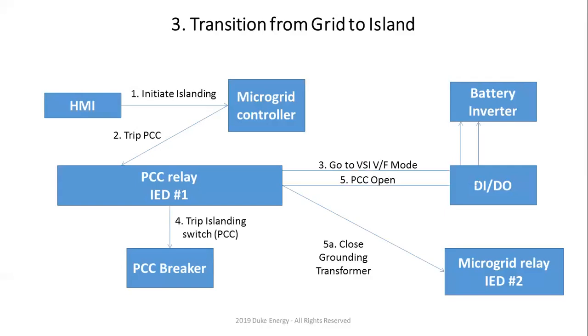You set the voltage at 1 per unit and you set frequency at 60 hertz. VSI VF mode is different, in that you just give it a range. So for the VSI VF mode, our frequency is plus minus 1 hertz from the set point, and voltage is plus minus 5%. And once we open, we have to close the grounding transformer. Remember, if you don't close the grounding transformer, you do not have proper protection. So you have to account for that. What happens if this fails? So this is the scheme that we use to island.